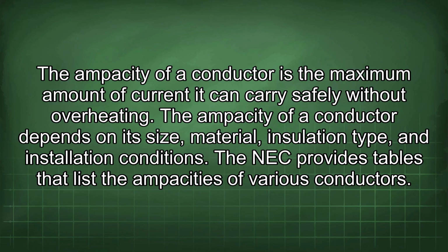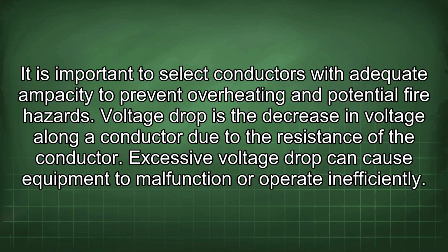The ampacity of a conductor is the maximum amount of current it can carry safely without overheating. The ampacity of a conductor depends on its size, material, insulation type, and installation conditions. The NEC provides tables that list the ampacities of various conductors. It is important to select conductors with adequate ampacity to prevent overheating and potential fire hazards.